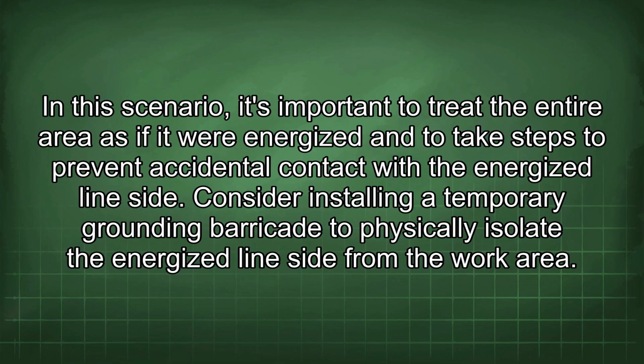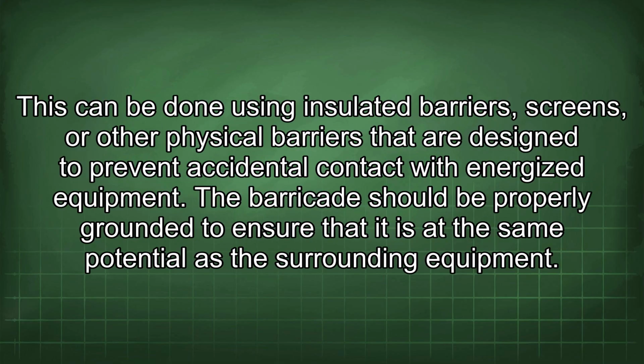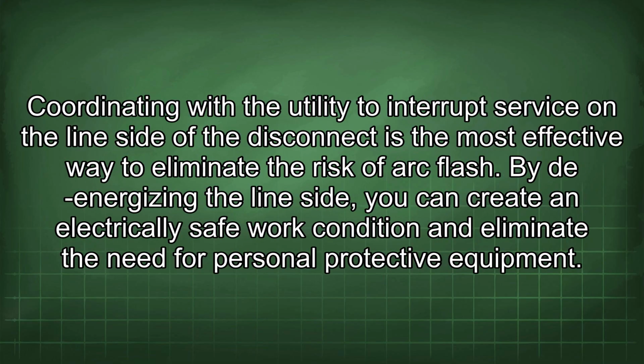Consider installing a temporary grounding barricade to physically isolate the energized line side from the work area. This can be done using insulated barriers, screens, or other physical barriers that are designed to prevent accidental contact with energized equipment. The barricade should be properly grounded to ensure that it is at the same potential as the surrounding equipment. Coordinating with the utility to interrupt service on the line side of the disconnect is the most effective way to eliminate the risk of arc flash.